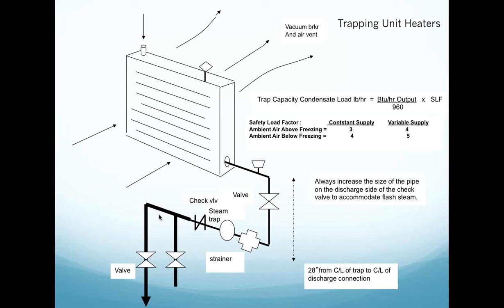I'm going to tip and pitch that unit heater just a tiny little bit, and if you need to know what that number is, I have the numbers available. But it's really interesting to me, in all the steam equipment that I get to see, that condensate and steam main lines are many times piped dead level flat. They should not be. They should be pitched. Steam systems should be pitched.